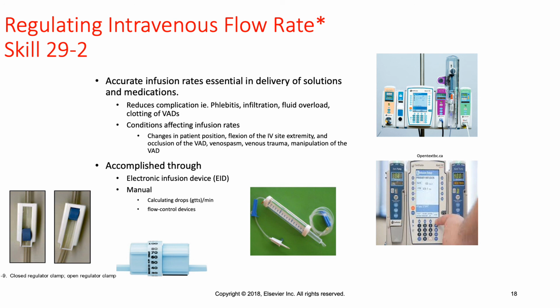If you want to ensure that your patient only receives a certain amount, you can put that into the chamber area, and then over that time period that you set, over an hour, for instance, that's all the patient would receive. The patient would be at less risk for fluid volume excess in this way, which is important in some patient populations, like our kids.